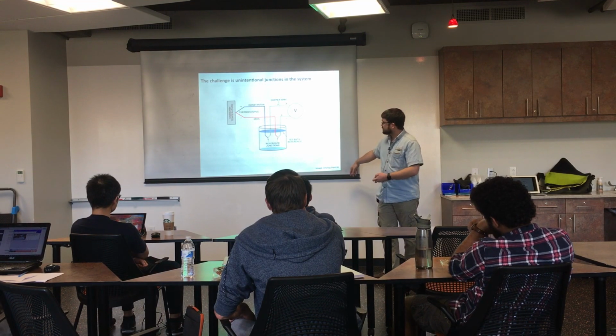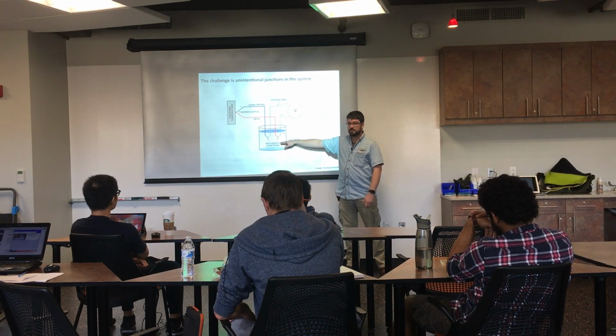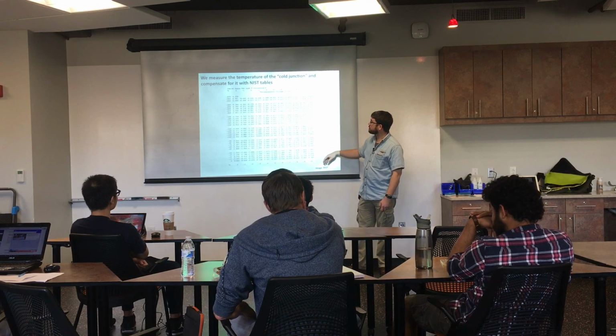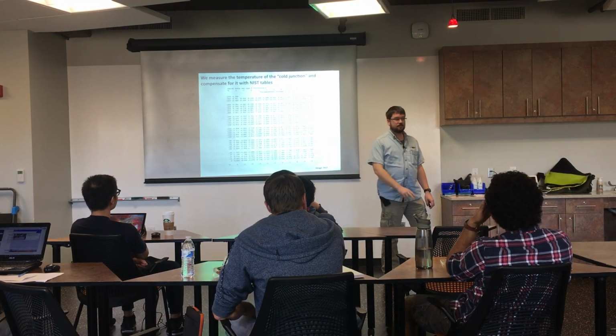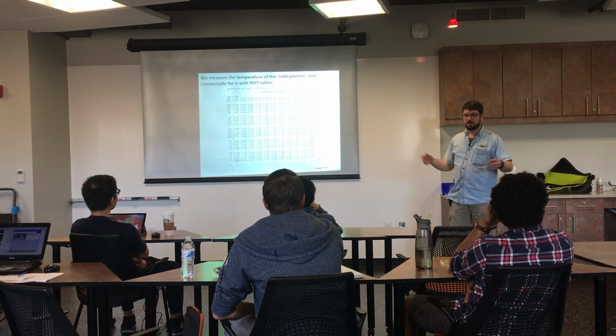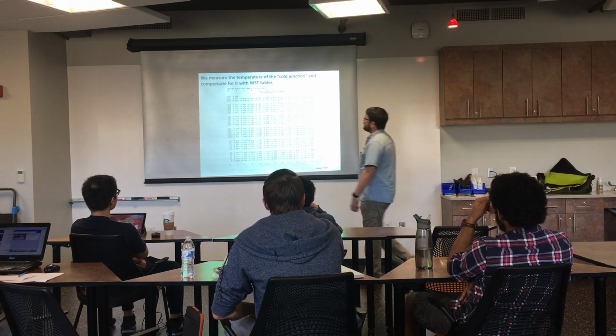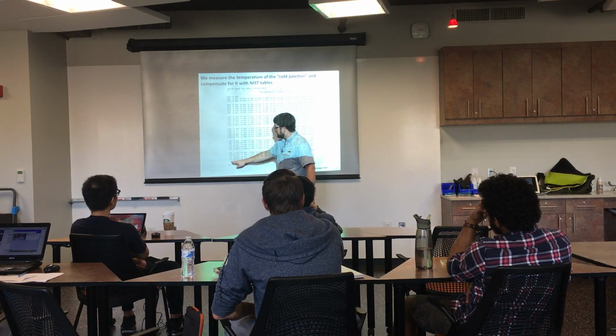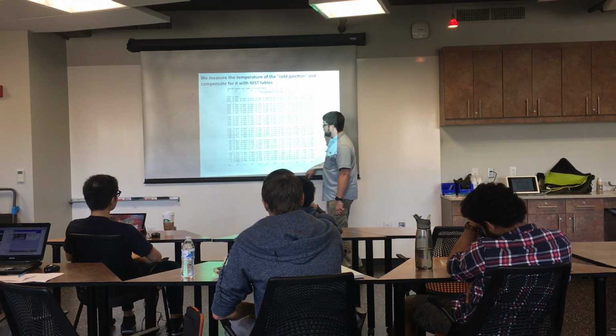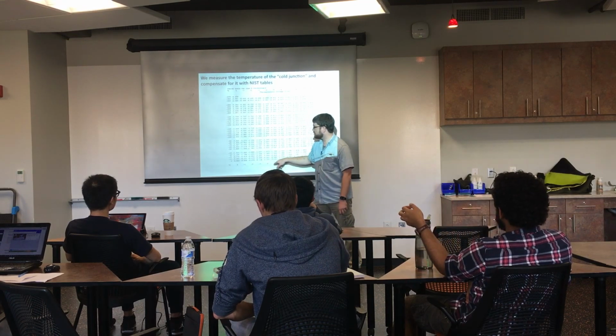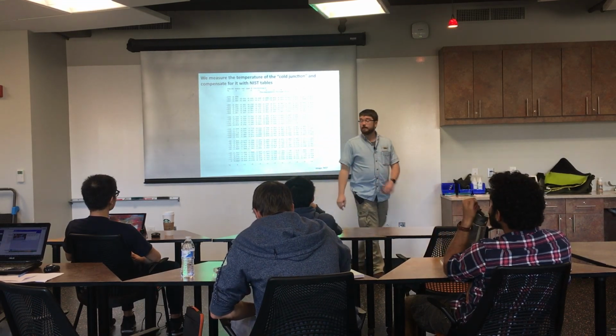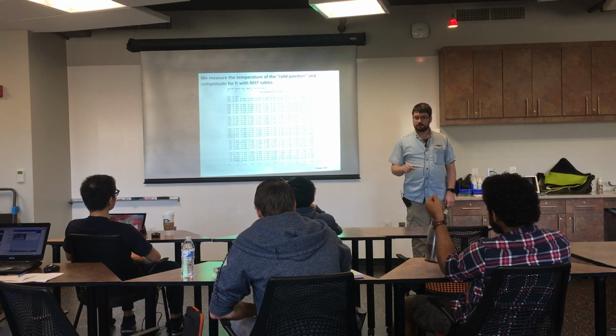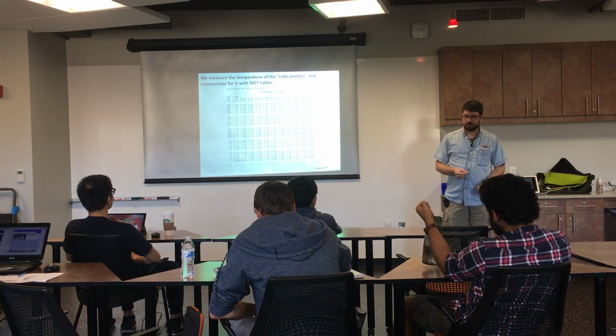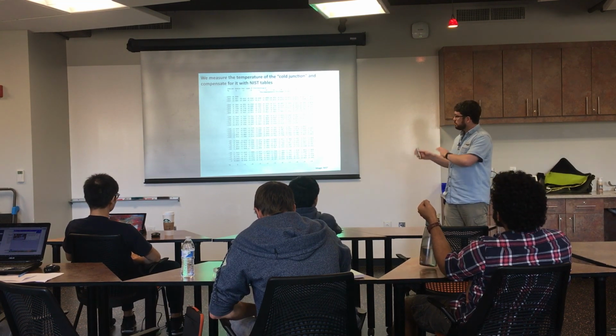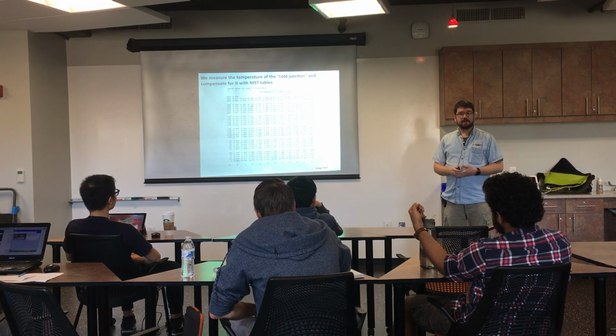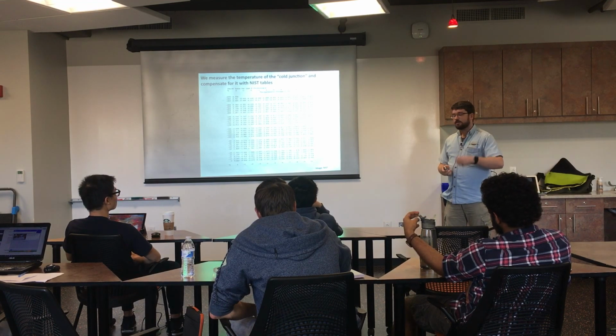So NIST, the National Institute of Standards, does this experiment for every thermocouple over its range, and they produce these tables. This is a section of one table. You can get them online. You can get them implemented in all kinds of programming languages. So here we're starting at negative 270C up to 0C, and then these are the increment of that. So 0, -1, -2, -3, and so on, and then -10, -11, -12. That is the output in millivolts of a type K thermocouple for that temperature. And it's very, very reproducible. So by using this table, we can back convert the millivolt that we measure to an actual temperature.